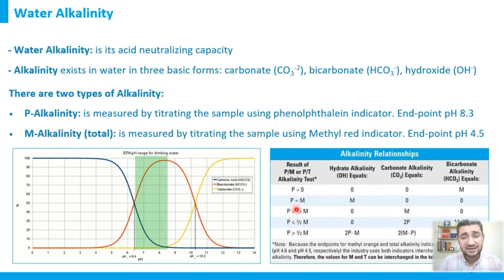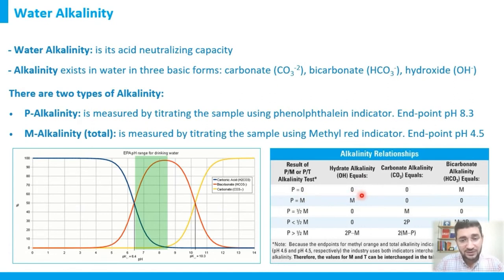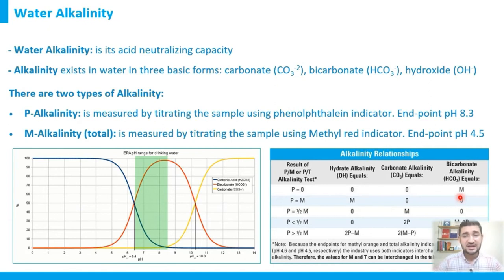Now let's look at alkalinity relationships. If P-alkalinity equals zero, then pH is less than 8.3, meaning there are no hydroxide or carbonate ions expected in the water. In this case, all alkalinity comes from bicarbonate. The total M-alkalinity is entirely due to bicarbonate (HCO₃⁻).